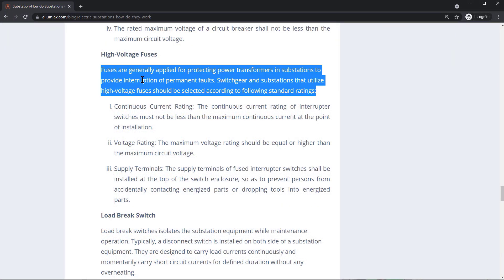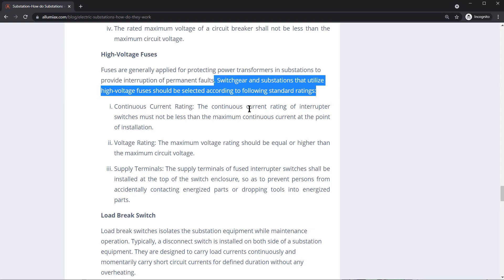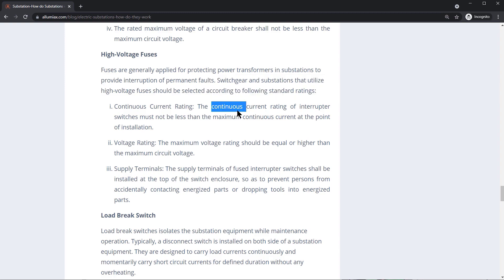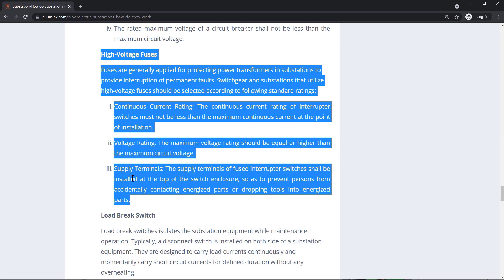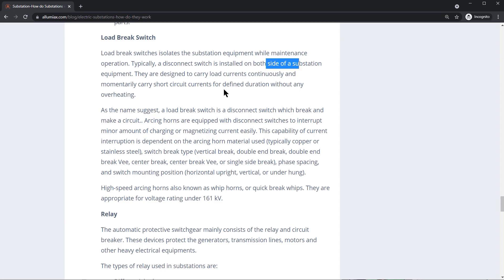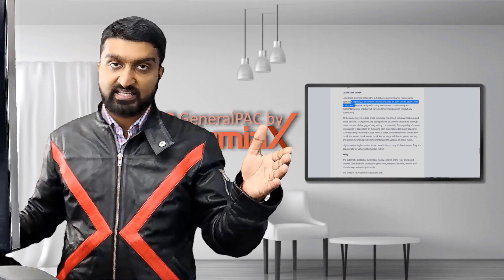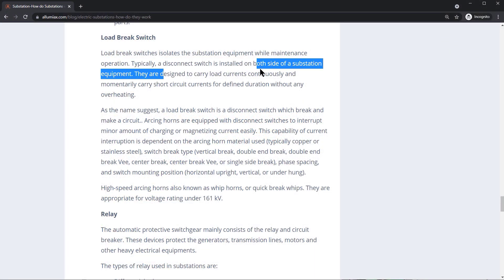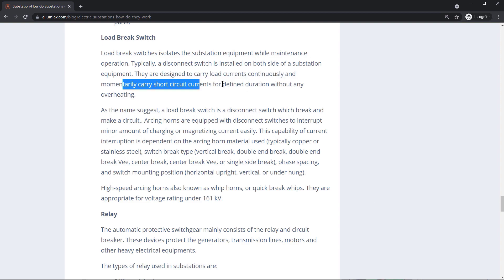High-voltage fuses are generally applied for protecting power transformers in a substation to interrupt permanent faults, and should be selected according to standard ratings. Typically, a disconnect switch is installed on both sides of substation equipment — on the line side as well as the load side. They're designed to carry load current continuously and momentarily carry short-circuit currents for a defined duration without overheating.